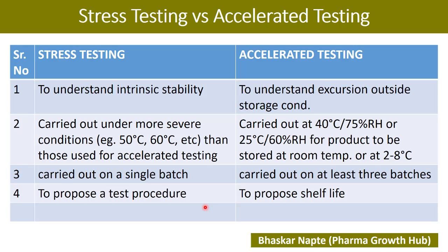Accelerated testing, on the other hand, is conducted to propose the shelf life of the product. There is a guideline available in ICH — Q1E — which covers estimation of shelf life for drug substances or drug products. According to that guideline, if you have six months of accelerated data, you can extrapolate to propose a shelf life. So accelerated testing is actually helping in proposing the shelf life.